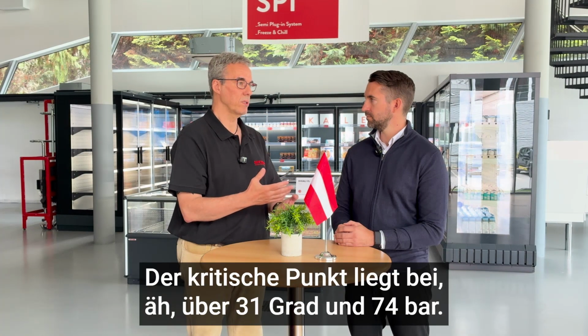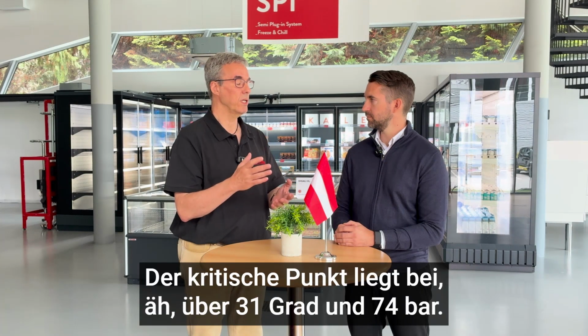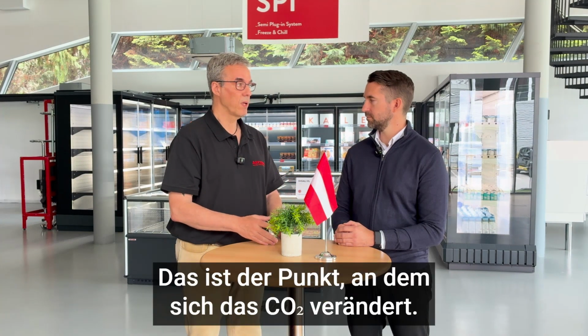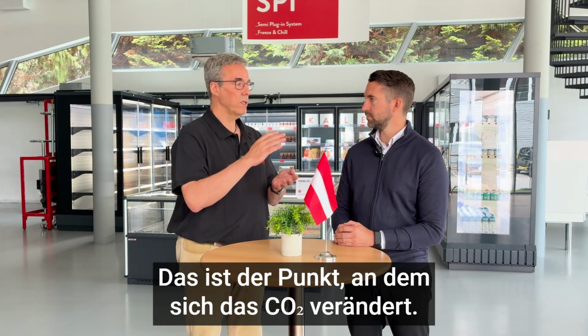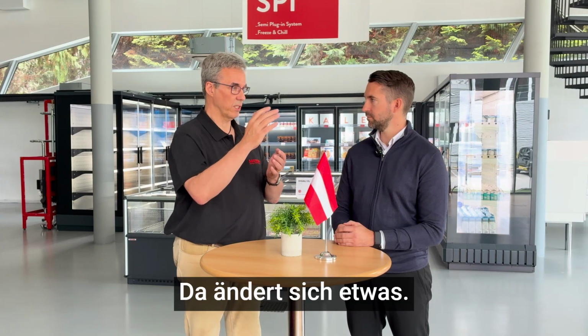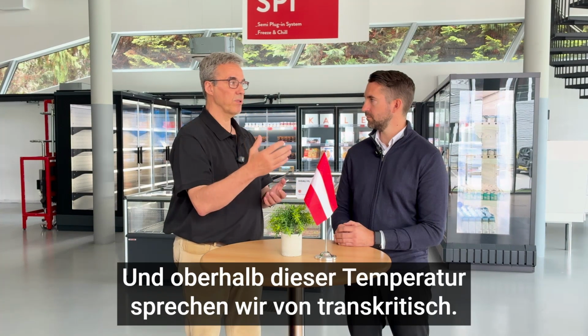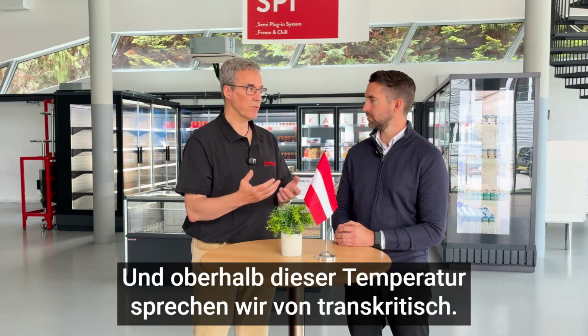The critical point is about 31 degrees and 74 bar. That's the point where something is changing. Below, we are talking about subcritical. And above this temperature, we are talking about transcritical.